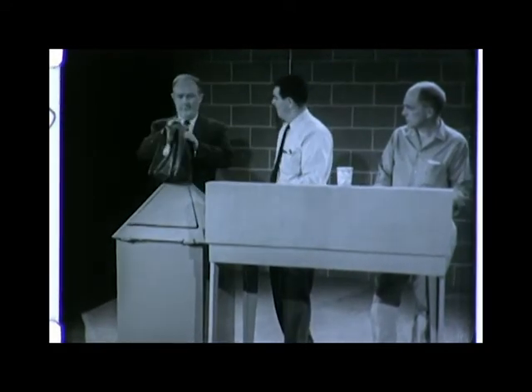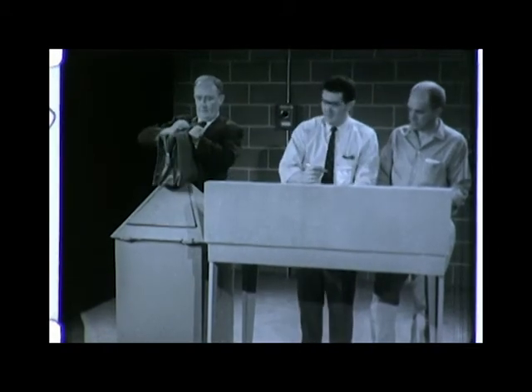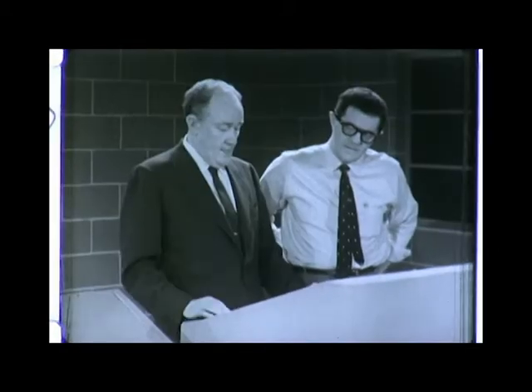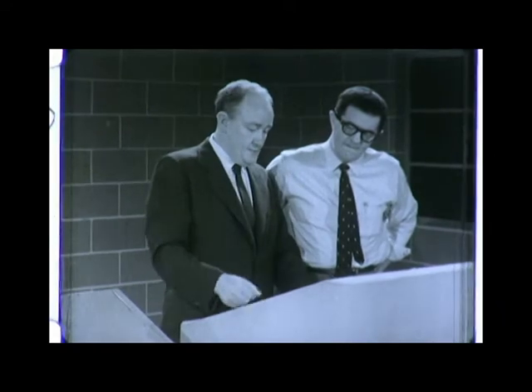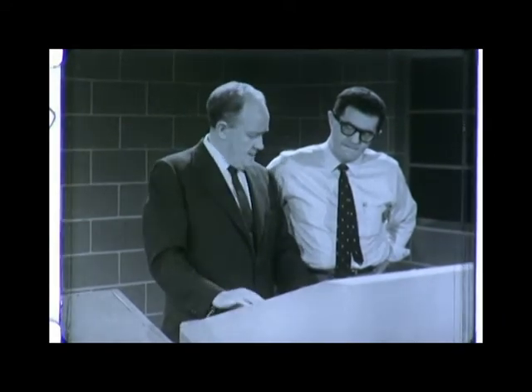Go ahead and finish whatever you have to do. I'll have to look through my bag for the bulletin. And these are frames taken right from high-speed movies of that test. On this one we see the test setup, conventional fuses in a standard box. Now you see the start of the short circuit, now it's building. And here comes the fuse right out of the box in pieces.